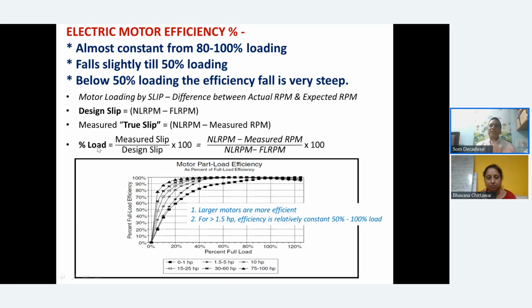So if the motor loading is less than 50%, maybe you can even run that motor in star mode. You can reduce voltages, especially on centrifugal machines, by that. People do this permanently. If the loads are not there and you have already taken a higher kilowatt motor, and you don't want to invest in replacing it with a smaller horsepower, fine, you can even run the motor in star if you have all 6 leads coming out in the terminal.